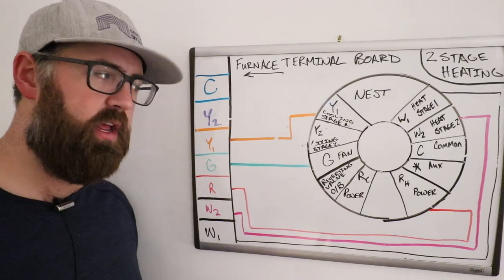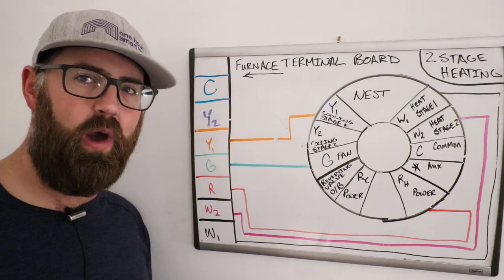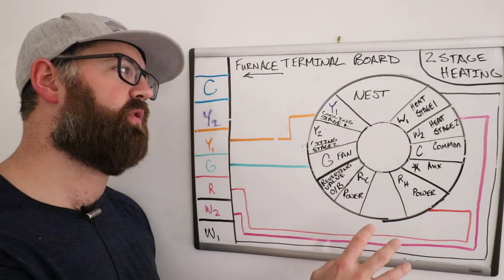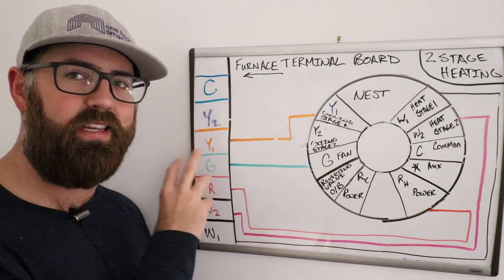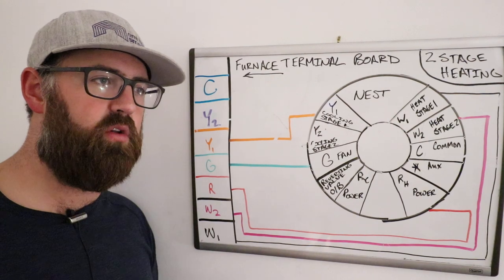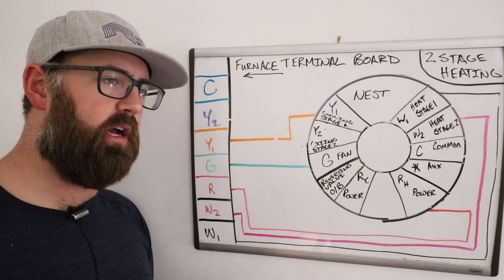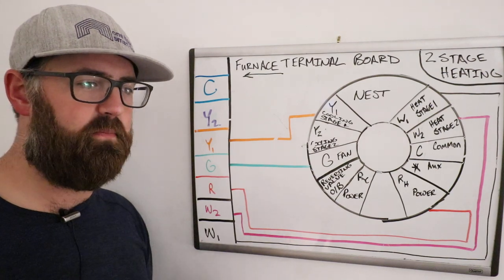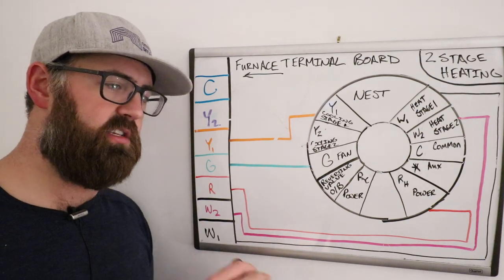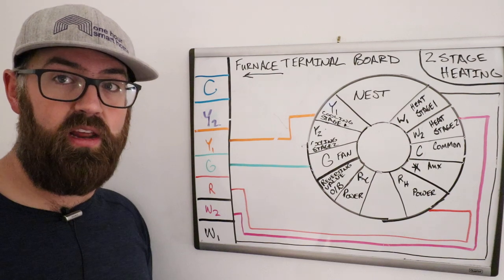So this kind of shows you the wiring diagram for a Nest thermostat. We've got a couple other questions or comments down below. Go ahead and post those. We've got other videos that show you how to do this and go even more in-depth with the Nest thermostat. But if you didn't take a picture of your Nest thermostat and you don't know what the wiring should be for two-stage heating, just go back to your furnace, see what terminals you have on there where the wires are already connected, and you're going to know how to connect this. Now, let's say you're setting up a brand-new house with a furnace or an HVAC tech. None of these wires will be connected. So how do you know what to do? Well, you can just follow along this diagram, or you can look in the manual for that HVAC furnace, and you can follow the same instructions that you would follow for a normal two-stage heating and cooling application as you would for the Nest thermostat. There's nothing unique about it. It works just like a normal thermostat. It just has smart technology built in and a Wi-Fi connection.